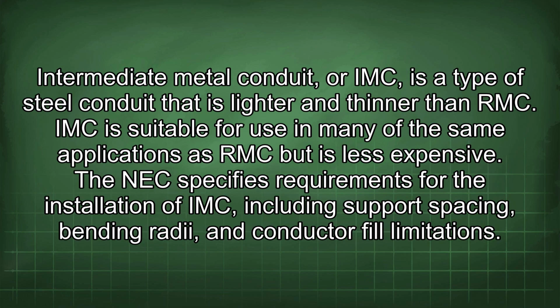Intermediate metal conduit, or IMC, is a type of steel conduit that is lighter and thinner than RMC. IMC is suitable for use in many of the same applications as RMC but is less expensive. The NEC specifies requirements for the installation of IMC, including support spacing, bending radii, and conductor fill limitations.